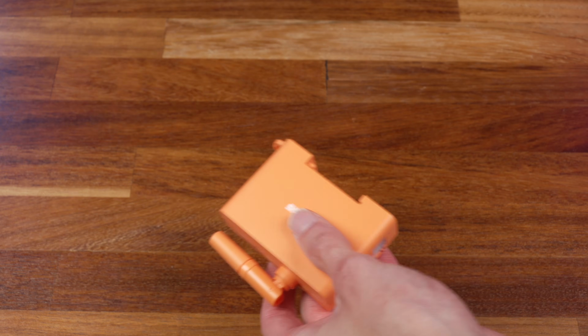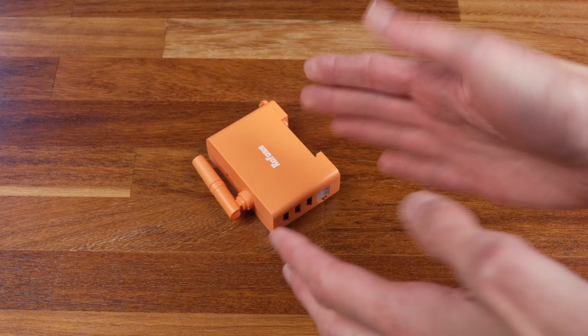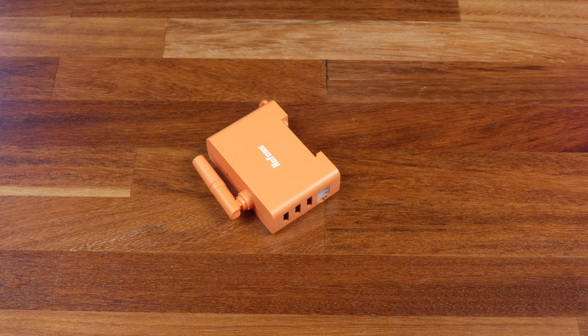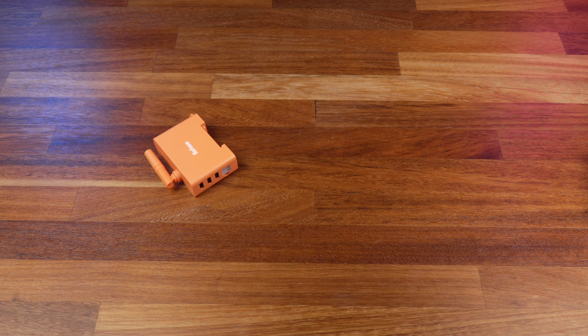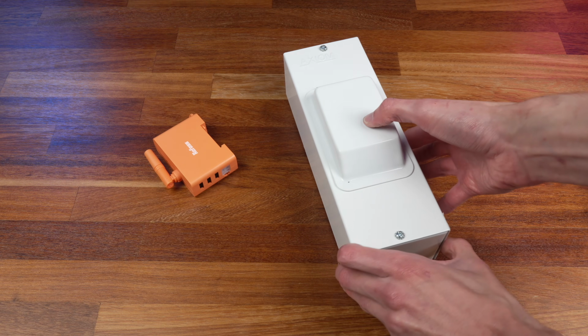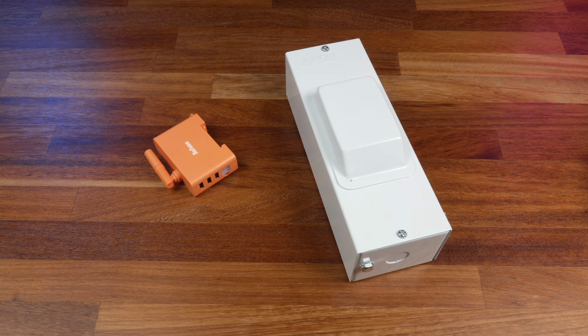So that would make it a bit awkward to install into an existing board, since you'd waste an extra space next to this, and you'd probably also then struggle to fit the blank modules around it, which could leave gaps in the front of the board. I don't think things are quite as strict as this in the rest of Europe, where it seems a lot more common to mix different brands inside a distribution board, but just to be on the safe side, especially since this being an electronic device will introduce additional heat into the board, I'm going to install it in a separate enclosure next to my consumer unit, and we'll take a look at that later in the video.